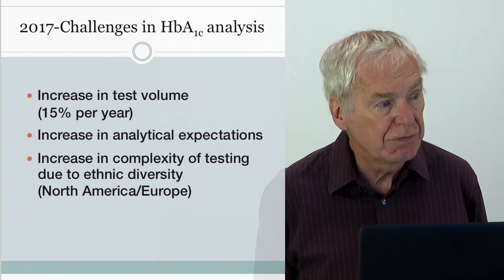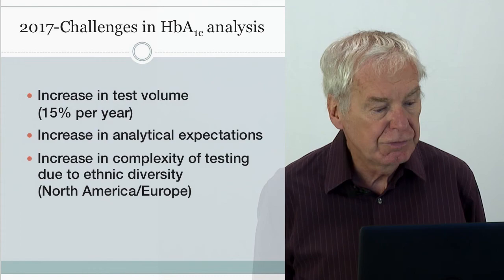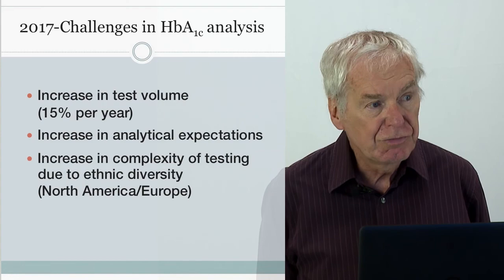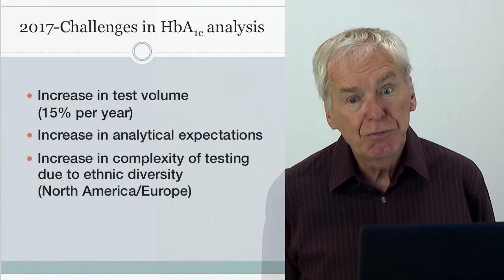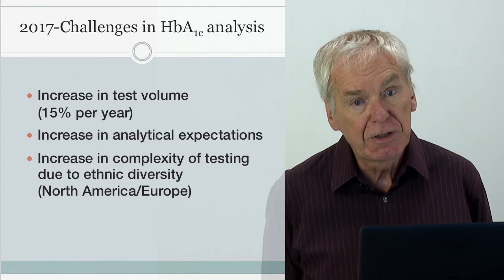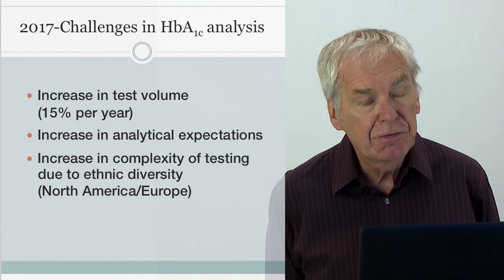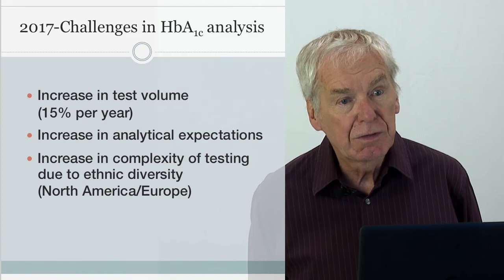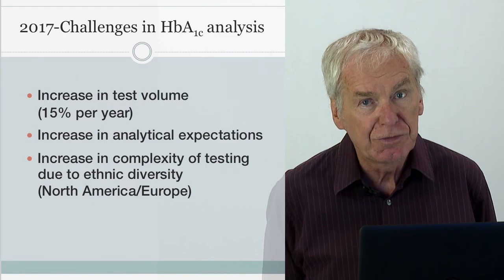We have seen a large increase in test volume. In our laboratory it is one of the fastest-growing tests, increasing by about 15% per year. The second challenge has been increased analytical expectations — the precision level demanded of A1c analysis is now much stricter. At one stage 3.5% within-laboratory CV was adequate; now 2% is required. The third challenge is increased complexity due to ethnic diversity, with a large increase in hemoglobin variants that challenge our analytical systems.